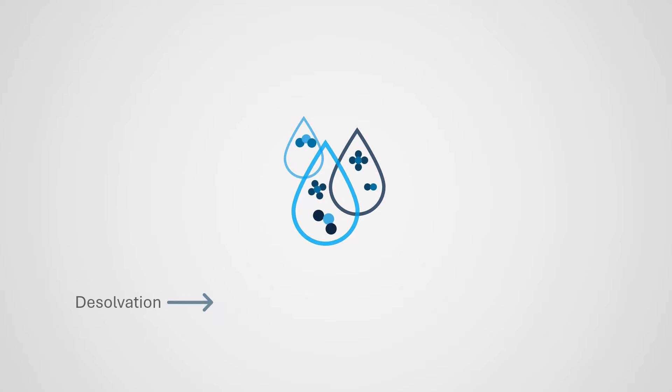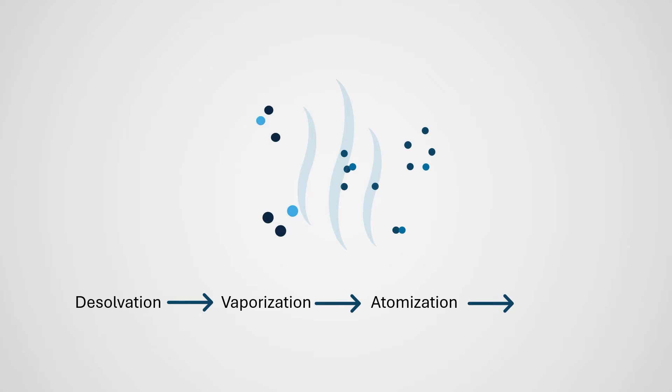Upon entering the plasma, the solvent evaporates, then the sample is vaporized, meaning it enters the gas phase. It's atomized, meaning molecules are broken down into individual atoms and simple polyatomic molecules, and then ionized. Positive ions strongly dominate.